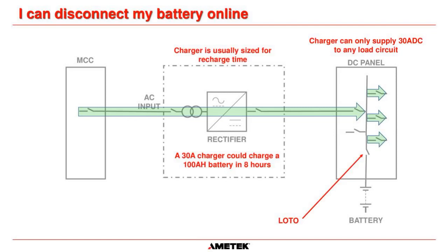If you have a loss of power and the battery discharges into the load down to 105 volts DC, then the power is restored and the battery charger outputs at 135 volts. What's the voltage on the bus? Very, very good question, and I'm glad you pointed out that I didn't answer that. And the answer is, it depends. It depends if the charger is rated for the full load current, just like we discussed with John's question.